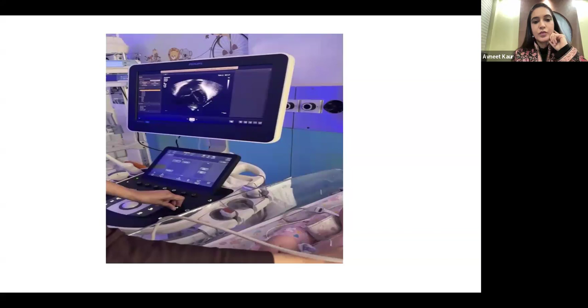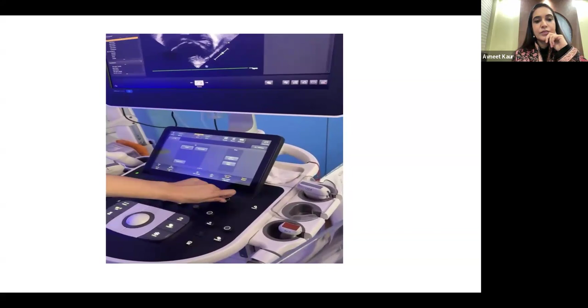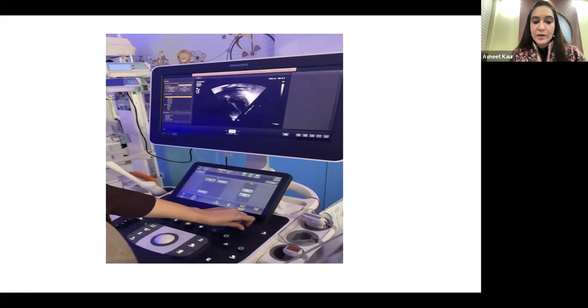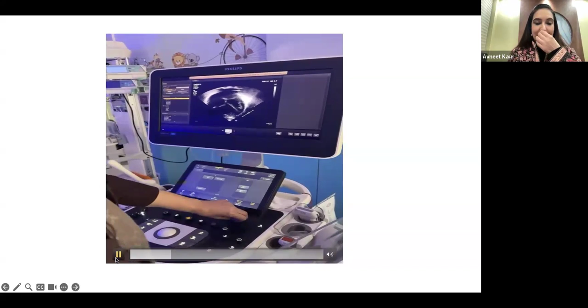Our image. Now what we want to see is that we have focused it better. Now we can adjust the sector width of this image, as Dr. Kamal had said that the temporal resolution can be adjusted by adjusting our sector width. So this is how we can have a reduced sector width and we can have a better temporal resolution. So some parameters help to increase our frame rate. So when we reduce the sector width, we have a better frame rate of the image, and it helps in a better resolution, which is the lateral resolution. So if we reduce the sector width, we increase the frame rate of the image. Okay, so this is our 2D mode.